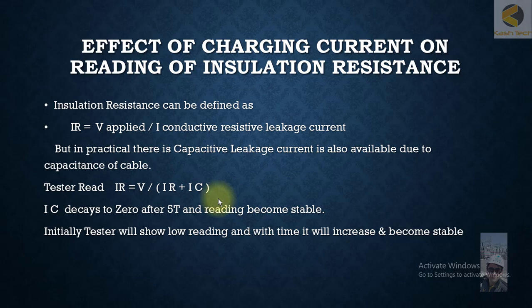If you are testing a very long cable, you need a powerful testing equipment with a high rating. For example, if you have a 5 kV megohmmeter that is very small and can only supply a small charging current, that equipment may take hours to get a stable reading. So if you are testing high-power and long-range cables, you have to have a heavy-duty, more powerful tester — otherwise you may have to wait hours and might not be able to get correct results.